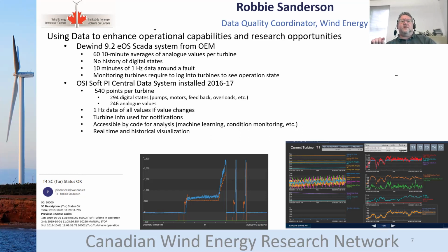The first two, the orange line and the blue line, go into the OEM SCADA system, showing the values they should be. But the actual piece of equipment controlling the turbine wasn't getting that input, and that was missed in the SCADA system, something we were able to pull out with this new barrage of data coming in.